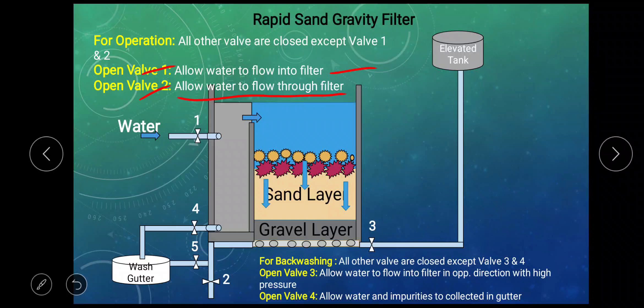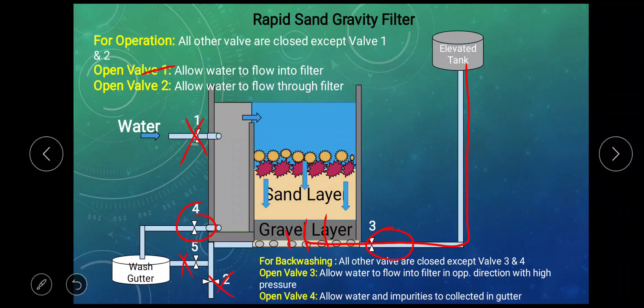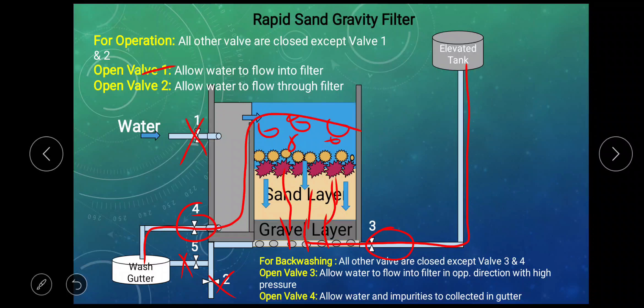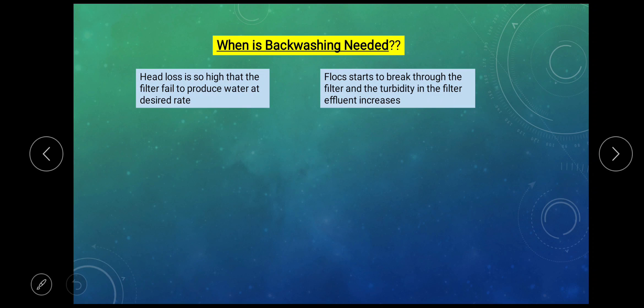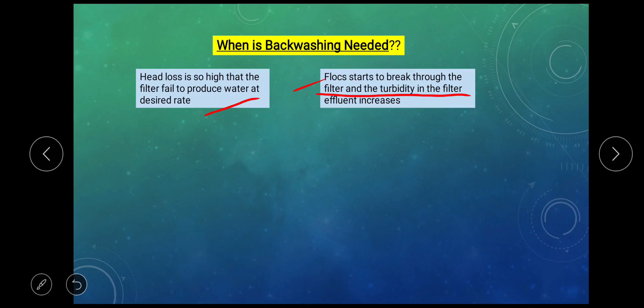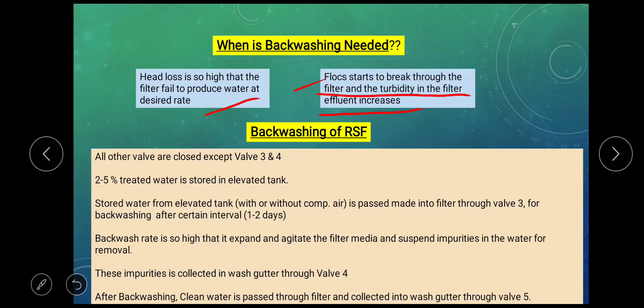Cleaning of the filter after every regular interval is done with back washing. Only valve number 3 and 4 are open. Water from the elevated reservoir with high pressure goes from the under drainage system and then to the gravel layer and sand layer. All the impurities are suspended in the water and collected from valve number 4, which enters into the wash gutter. Cleaning of rapid sand filter is done under two conditions: one, when head loss is so high that the filter fails to produce water at the desired rate, meaning when the filtration rate reduces drastically; or when the flocks start to break through the filter and turbidity in the filter effluent increases, meaning impurities may be seen in the filter water. This is how back washing is done.